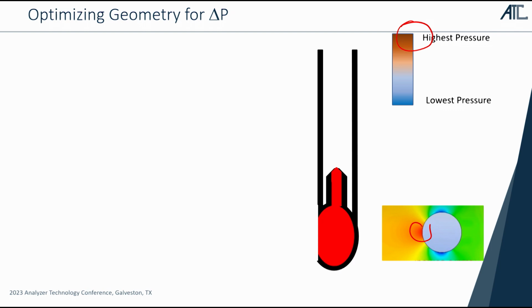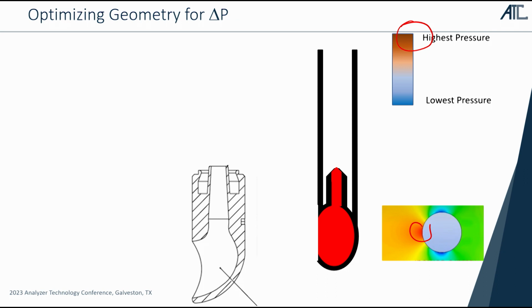So what we start out with is a probe, and it has a mechanical insert in it, and part of that mechanical insert is a thing which we refer to as the scoop. We call it a scoop because it looks an awful lot like a scoop; it looks like something I'd use to scoop dirt up. The unique thing here is that there is a very optimal curvature to introduce, because what we want to happen at that scoop is for fluid that's flowing along horizontally to flow around it and change direction by 90 degrees. When people just cut it off at an angle and let it impact on an object, some of the pressure, the available delta P, the available energy that we could use for driving flow, is lost in the turn. So we did a whole bunch of computational fluid dynamics to try to work out how to optimize what happens within this region. I drew that a lot more crudely here.